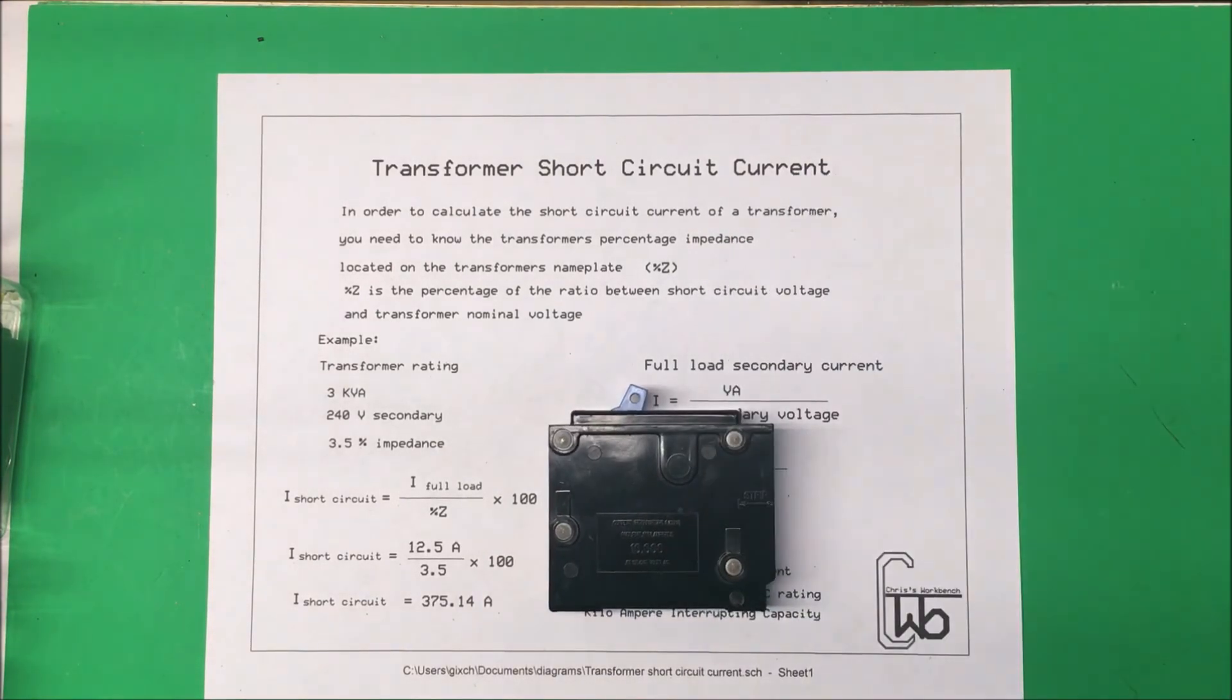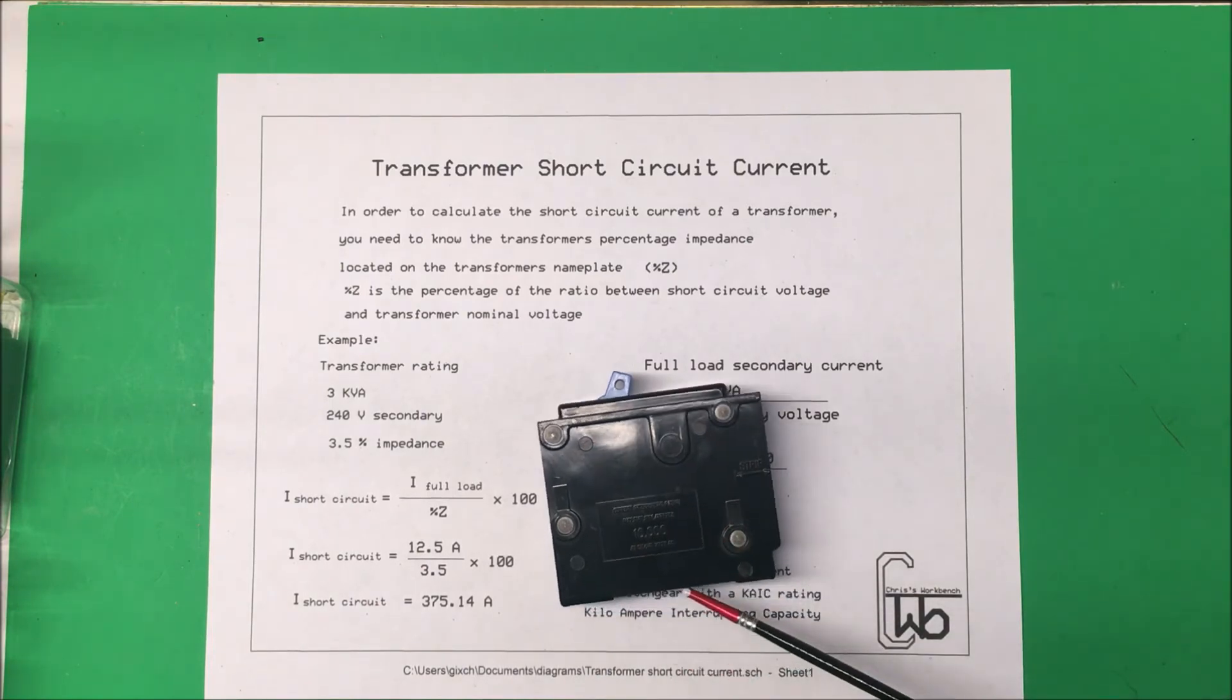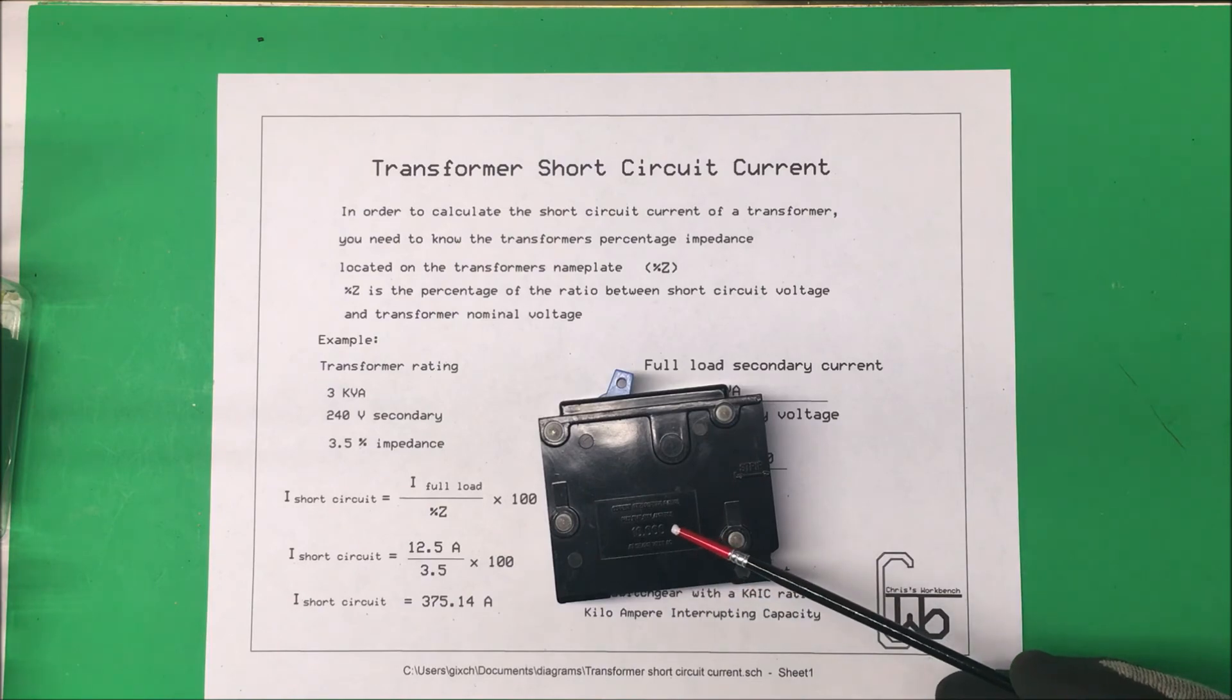Now most circuit breakers and fuses are rated well over that. I don't know if you can see this one, but this one has a KAIC rating of 10,000 amps, so well within the limit.